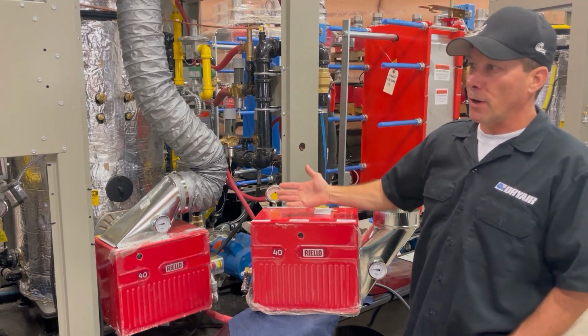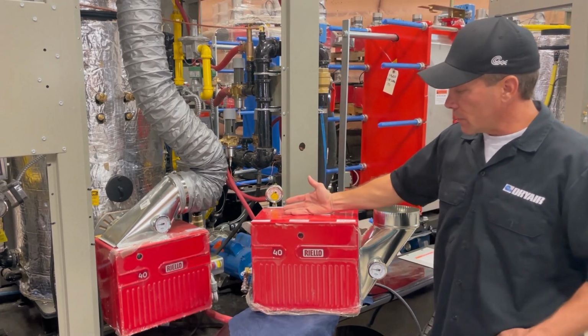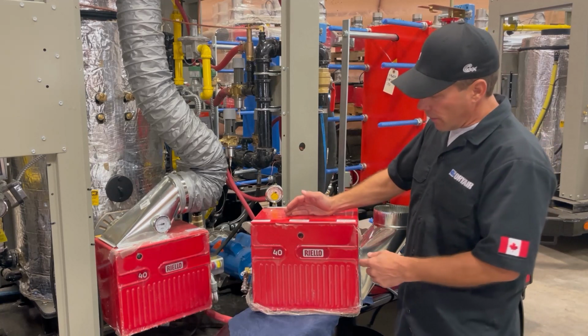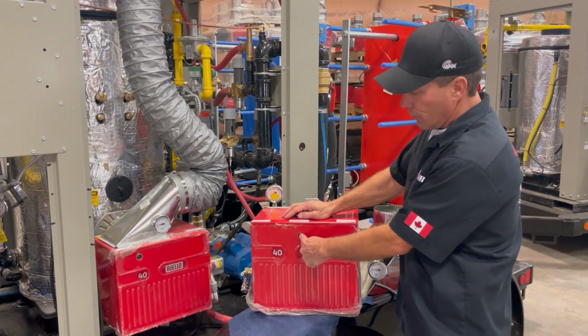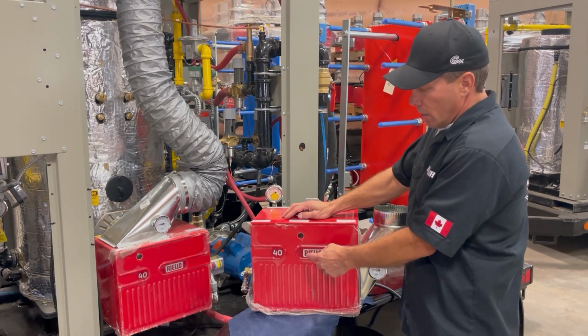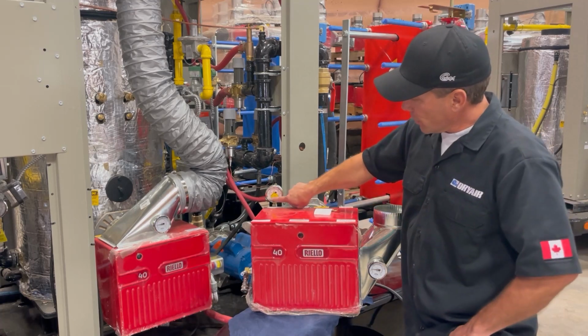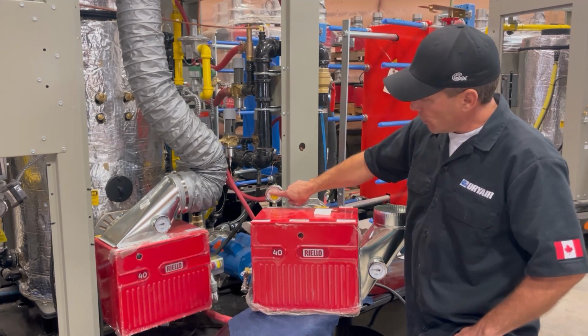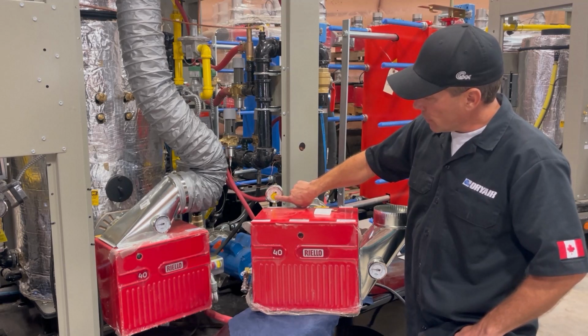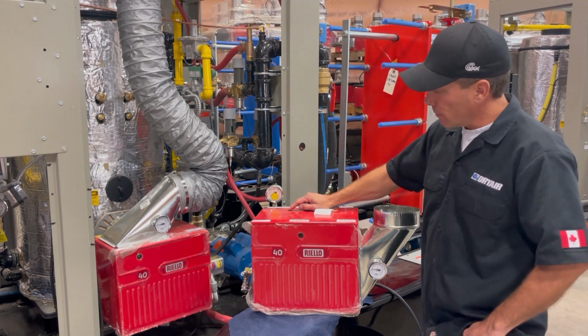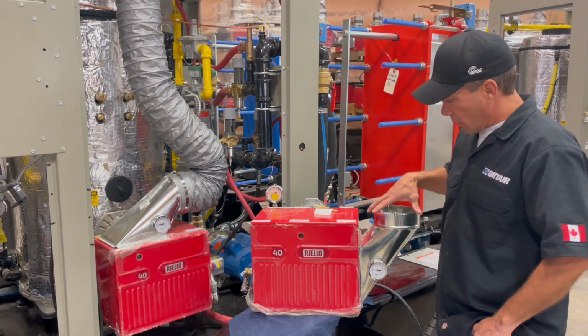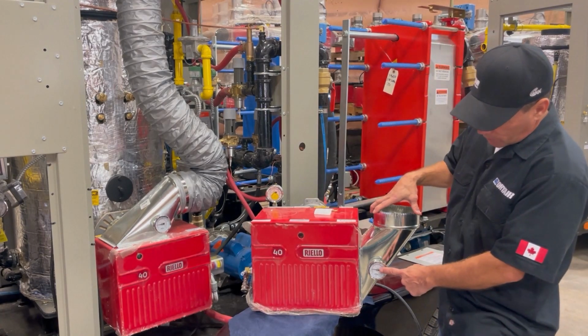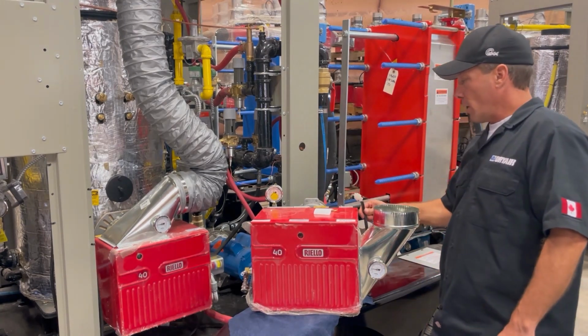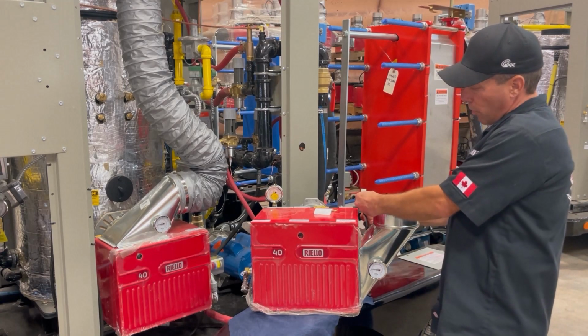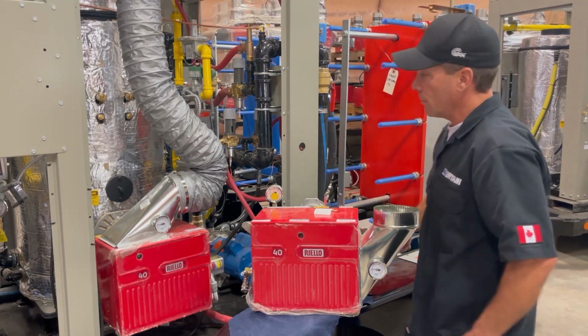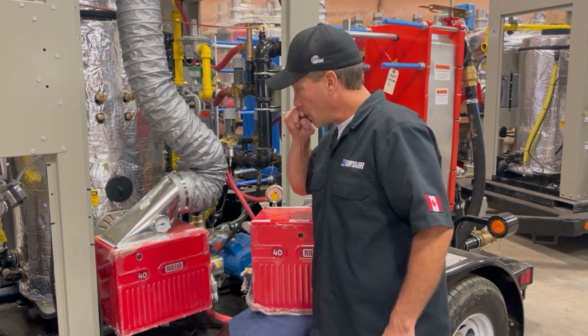So when you go to fire your burner up on your diesel side and it may shut off because of air in the system, you push this in for 3 seconds, let go, and it'll reset. Then you watch your gauge up here, it'll come up to pre-purge, and once it lights, the gauge will come up to where this sticker is showing where it should be. Air intake, this will read the temperature of air, and then you have a 4-prong wiring system that you have to plug in when you switch these out.